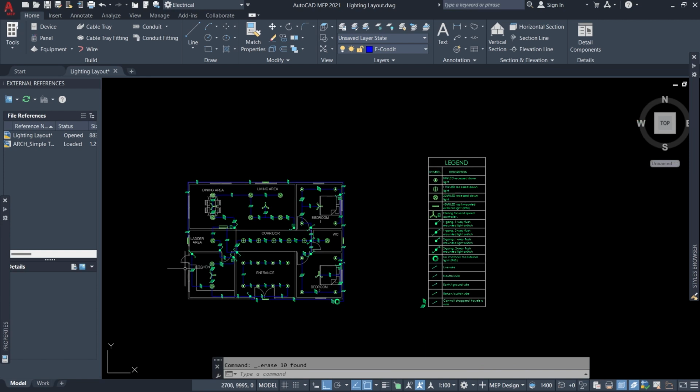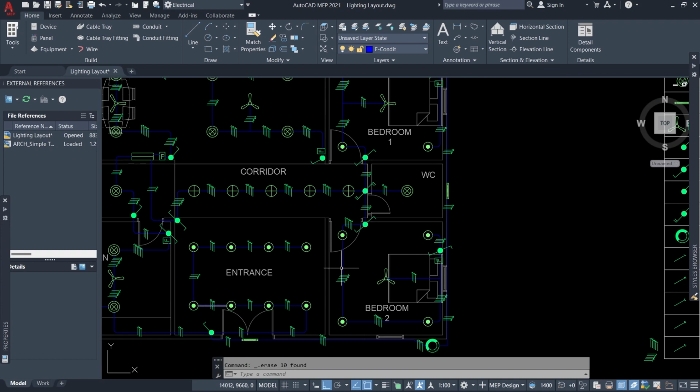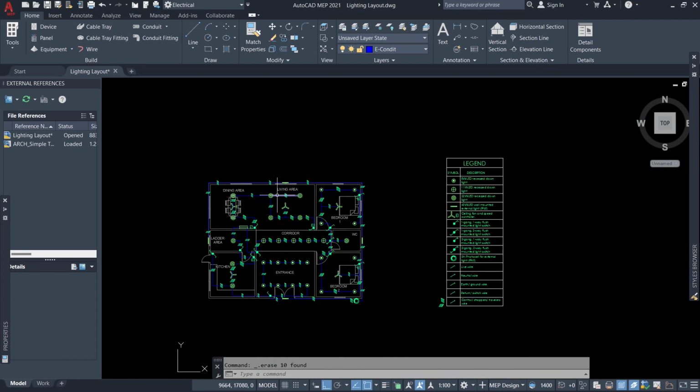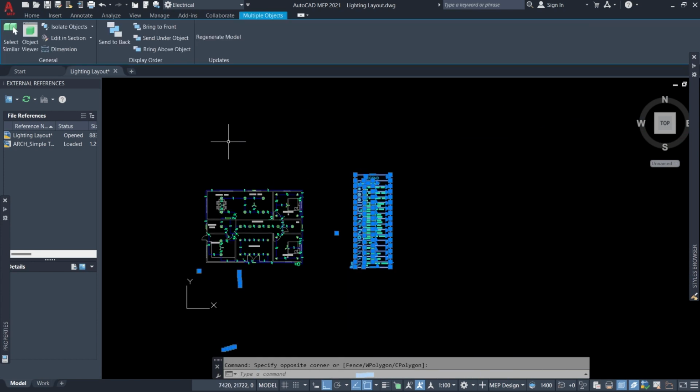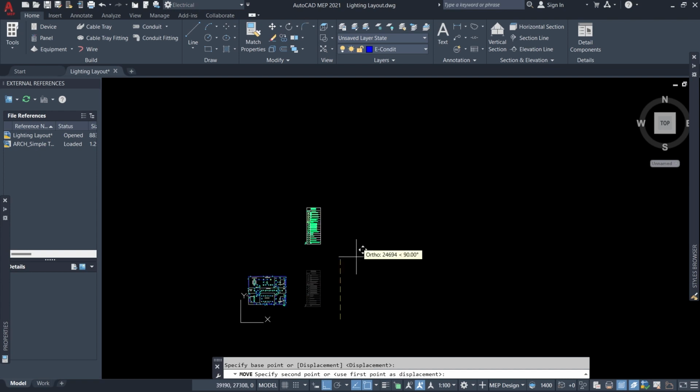So you can see that now we can tell what cable is in what conduit. If you should give this drawing to an electrician, he should be able to carry out this design practically. That is the goal and the aim of what we just did.